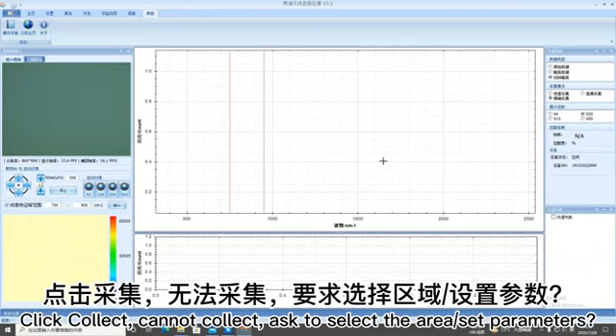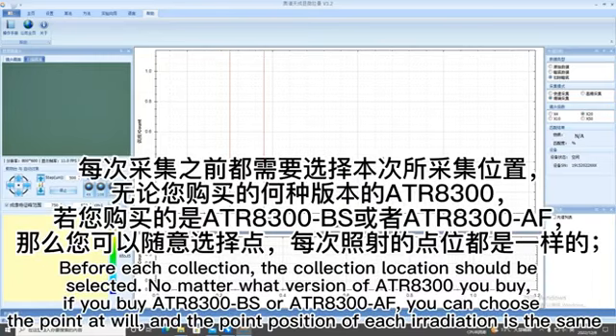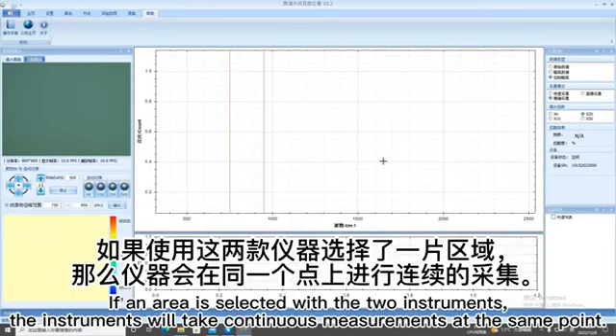Click collect, cannot collect. Ask to select the area and set parameters. Before each collection, the collection location should be selected, no matter which version of ATR8300 you buy. If you buy ATR8300 BS or ATR8300 AF, you can choose the point at will, and the point position of each irradiation is the same. If an area is selected with the two instruments, the instruments will take continuous measurements at the same point.